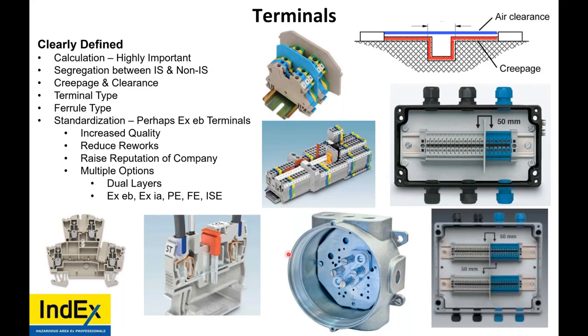So with these terminals, we get good creepage and clearance distance. See here, between IS and non-IS, you have to get 50 millimeter separation. You can do it via spacing or a divider. And once again, if you have two levels, you do have to have 50 millimeters between both levels and between the singular level.